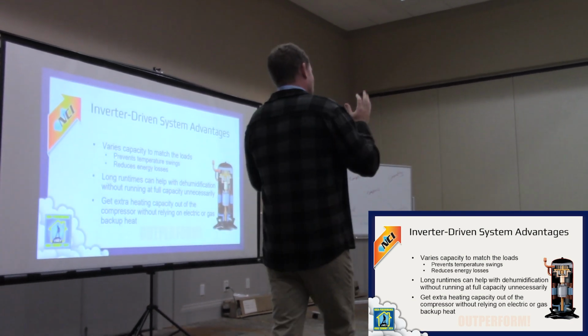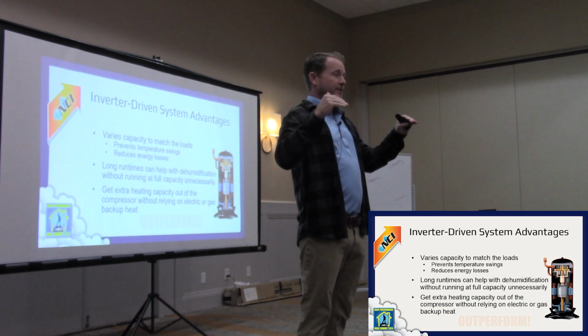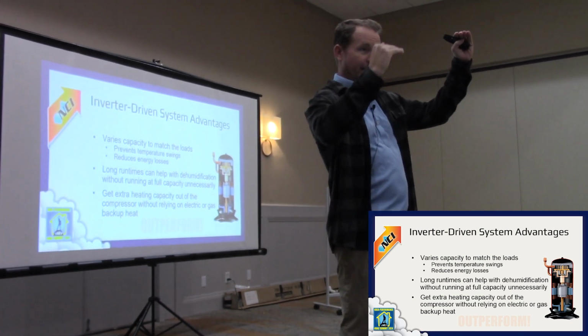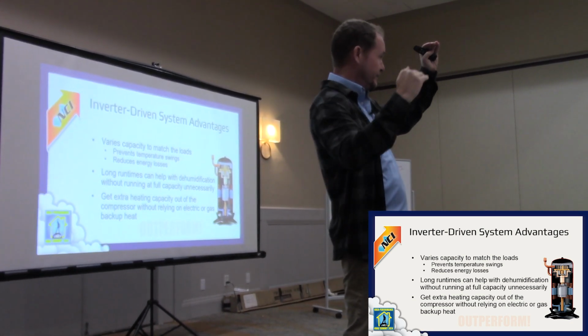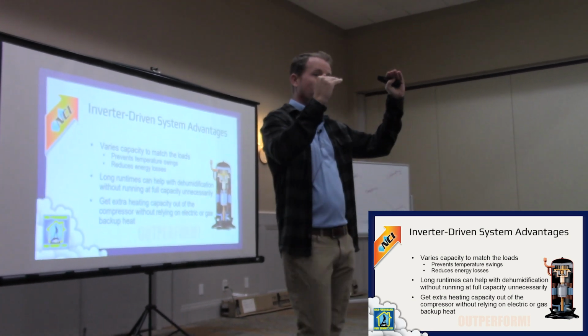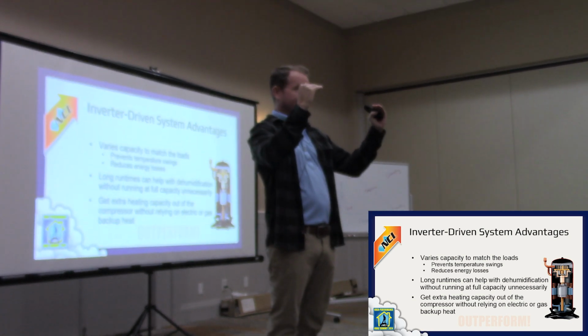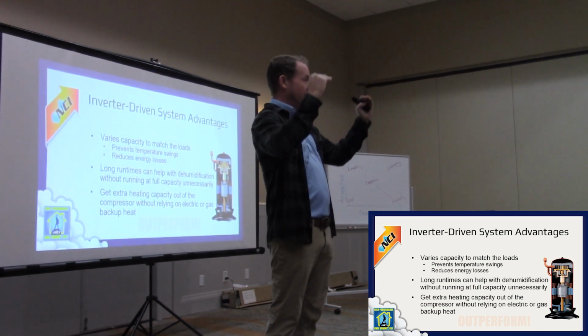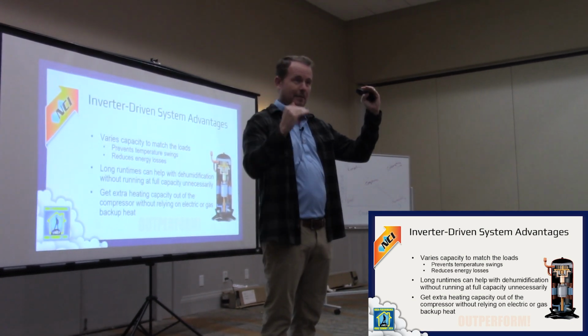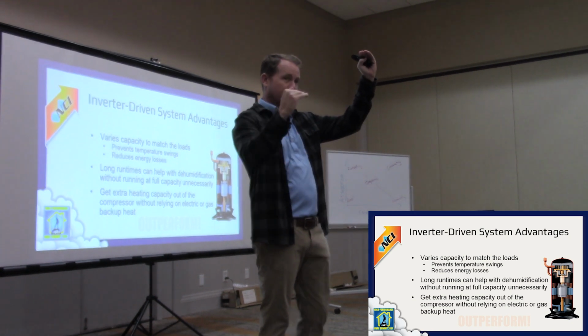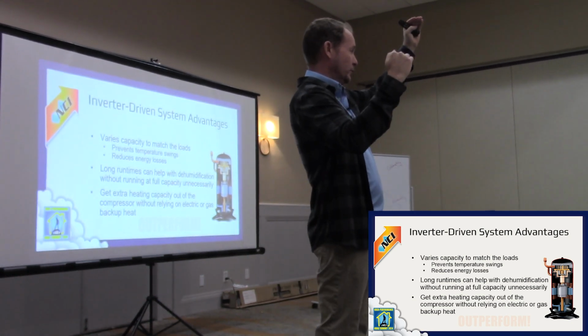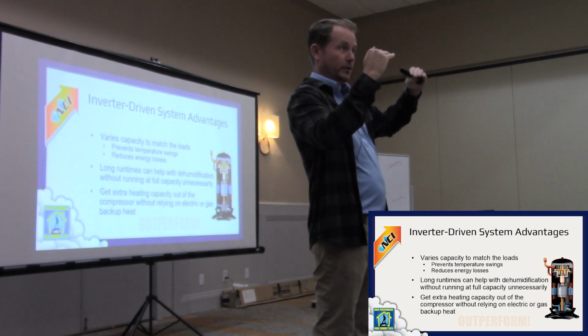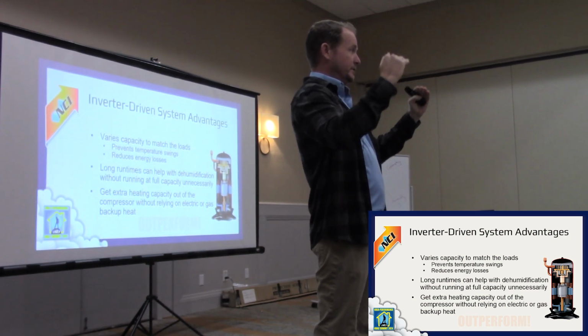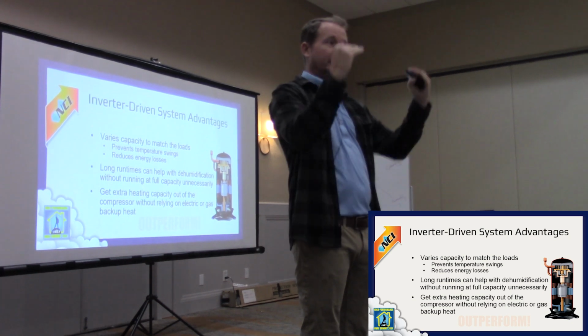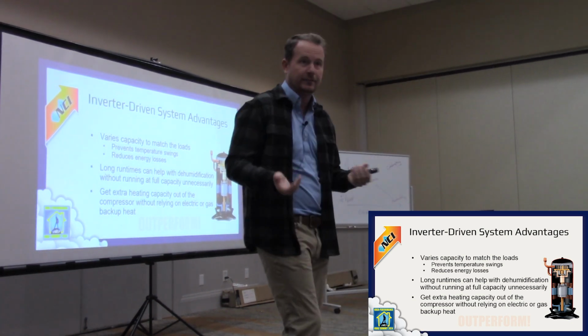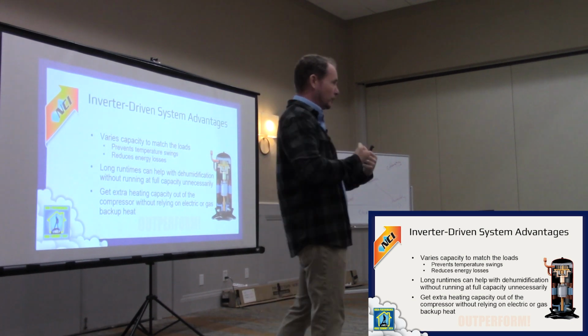Okay, fine. So theoretically, an inverter system should be great at this, because when we turn the compressor down, when we spin it slower, because we don't need as much capacity, we don't need to pump as much refrigerant through the system, we should be able to also slow down that blower at exactly the same rate, and then we always keep the same evaporator temperature. Does that make sense? If you pump less refrigerant and you keep the air flow the same, what happens to your coil temperature? Goes up, right? Creeps up on you. But if you drop your blower speed as you drop your compression, then you should be able to keep that nice cold evaporator coil, maybe 38 degrees, 42 degrees, in that range, where it's going to do a really good job of wringing moisture out of the air.